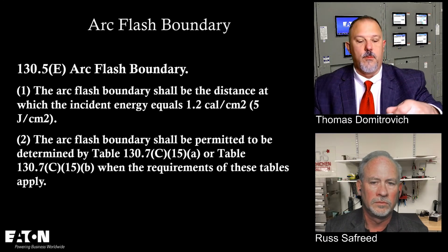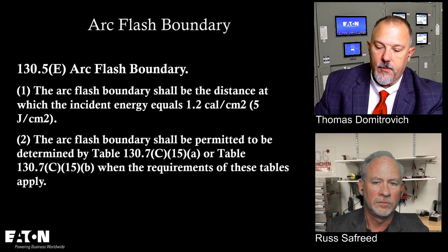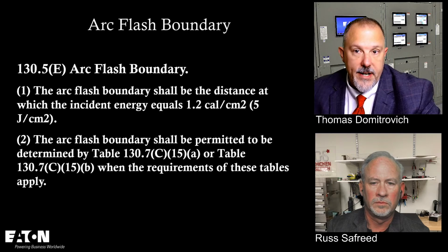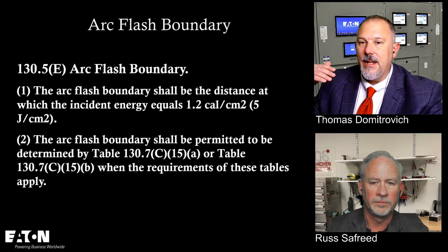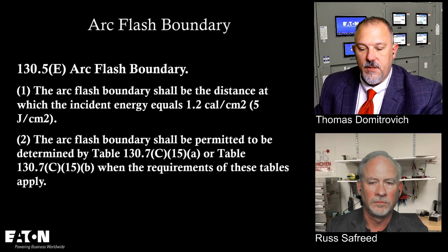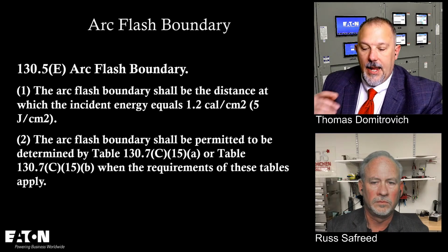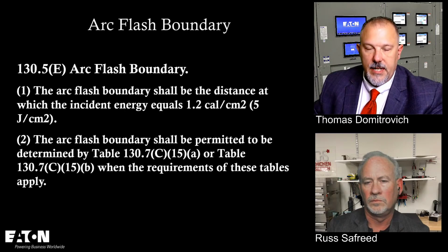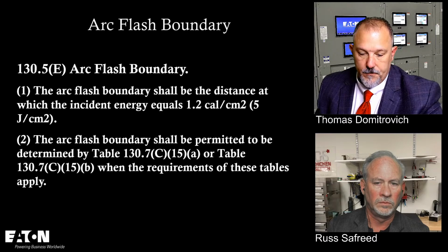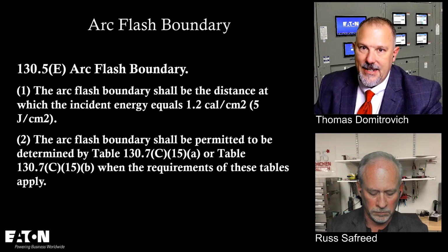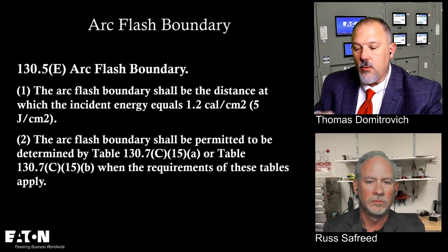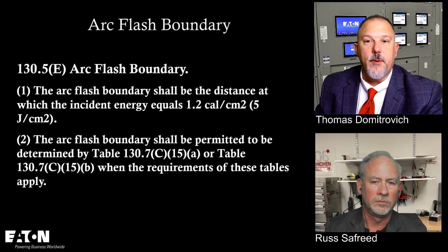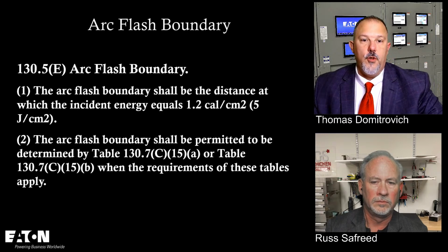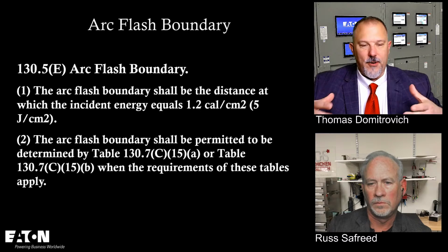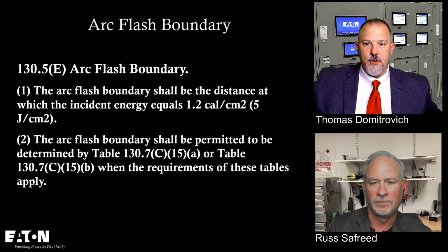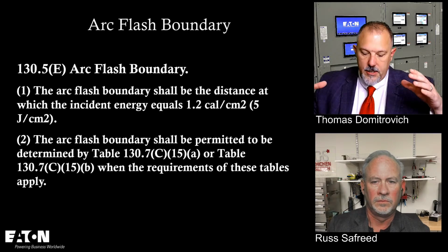I'll give you an example: a panel board, or other equipment rated greater than 240 volts and up to 600 volts. So take a 480 volt panel board. If you have 25,000 amps of bolted fault current or less, and you are downstream of a molded case circuit breaker or current limiting fuse, and an 18-inch working distance, you're in a PPE category 2, and your arc flash boundary is 3 feet. So you would draw a line, get those tapes and mark out your 3 feet around your work area, and use this table.